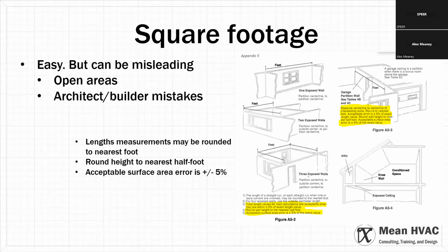There is a section in the manual J on how to measure a building, and the lengths of the walls, meaning basically the floor plan of the building, can be measured to the nearest foot. That's obviously going to create a little bit of noise in the signal. The heights can be rounded to the nearest half foot, although that's not usually a reporting problem because we're usually talking about floor areas, the thing people are checking. There is an acceptable surface area margin of error for the measurement of the floor plan, and it's plus or minus 5%. So if they're within 5% of the builder square footage, that should be an automatic pass. Just because something is a little bit off of that doesn't necessarily mean they did anything wrong.